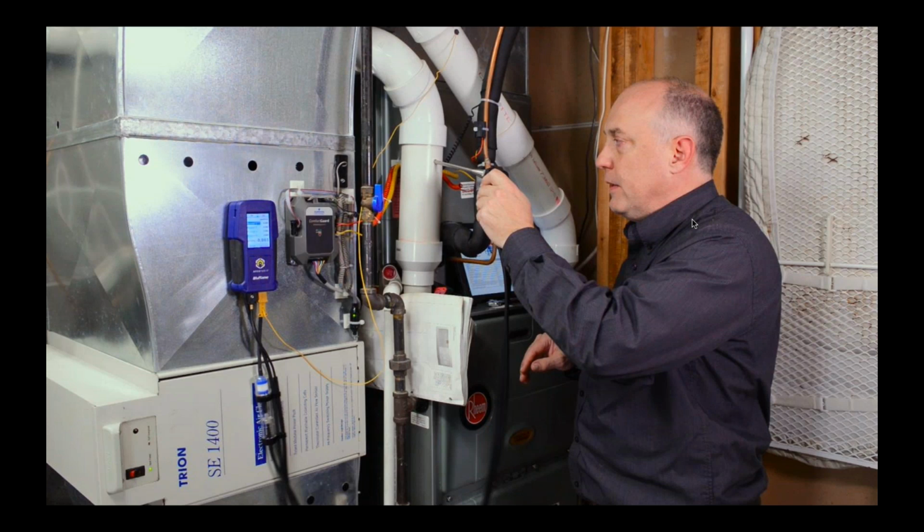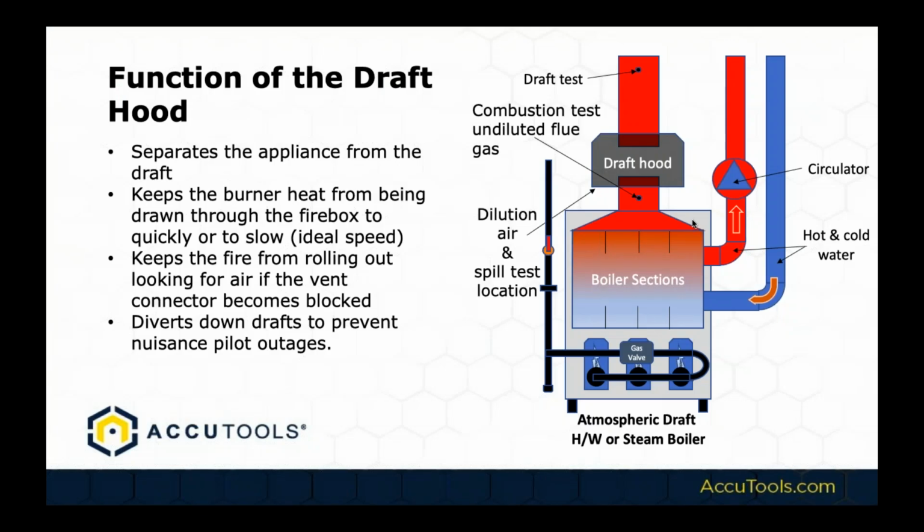The large pipe eliminates the friction or lowers the friction rate, but we need to neck it down before it goes out to push the exhaust gases far away from the house. And the job we were on, they actually had an overhang for an ornamental fireplace, and it was a pathway for CO to come back in the home because it was just sitting there right next to the house instead of exhausting out, causing exhaust gas recirculation problems. So again, a good use for the combustion analyzer.